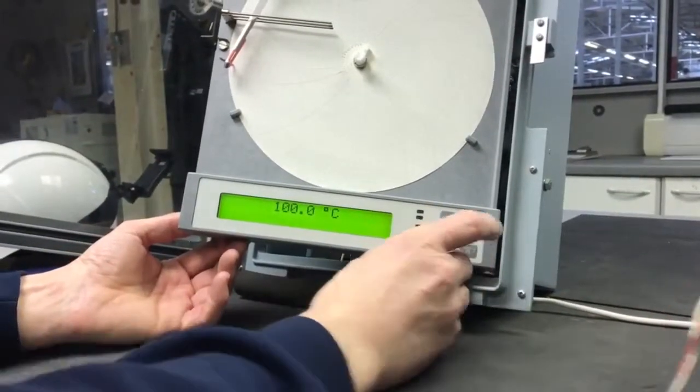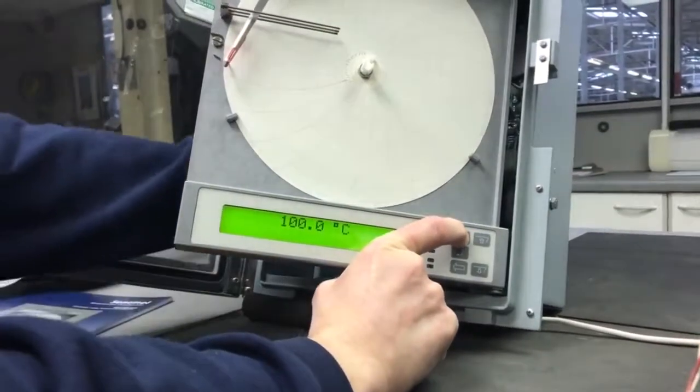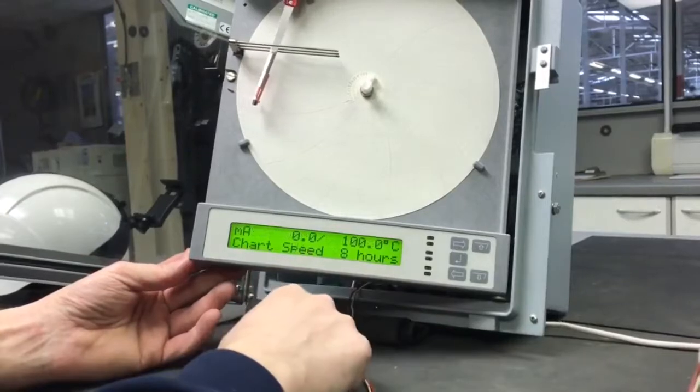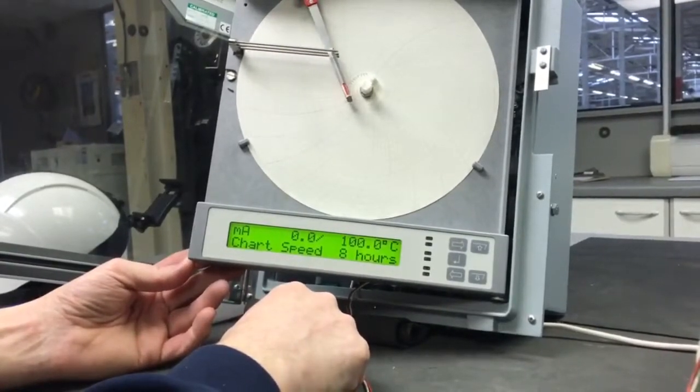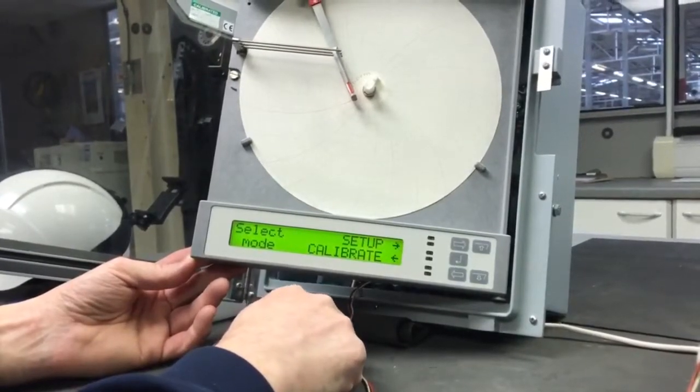We need to enter the setup mode. Press one of the arrow buttons, press and release the reset button, and release the front arrow button. The pens will drive to the bottom of the chart, then you get a message on the display: setup and calibrate.